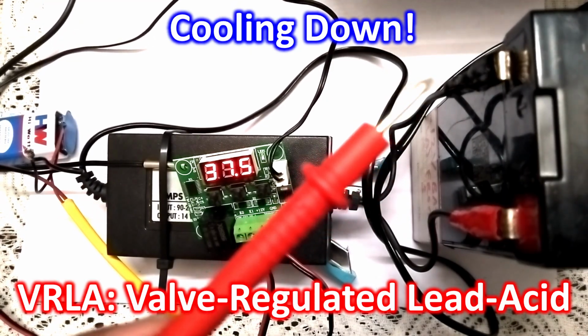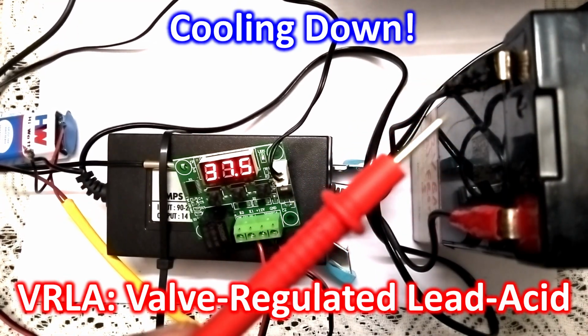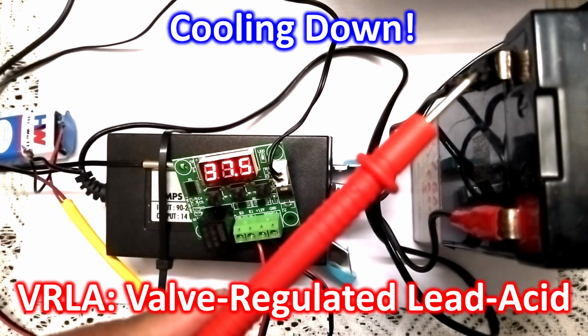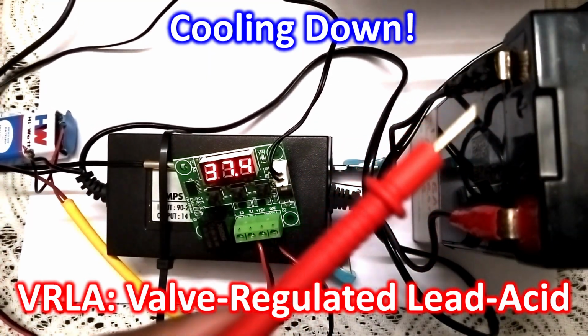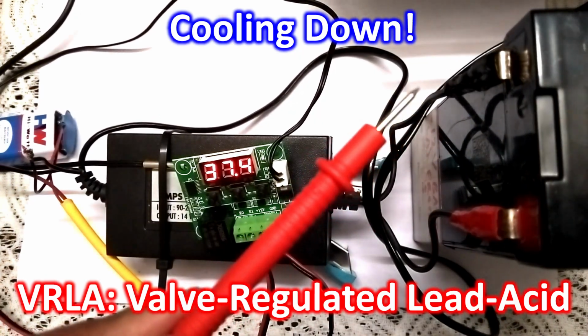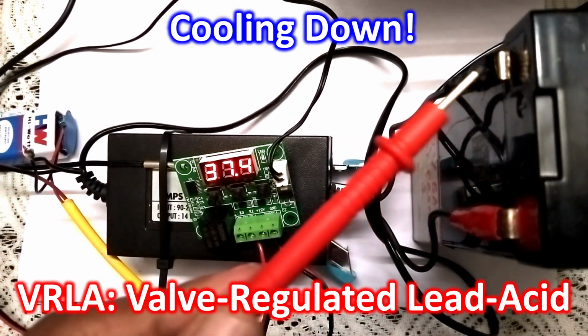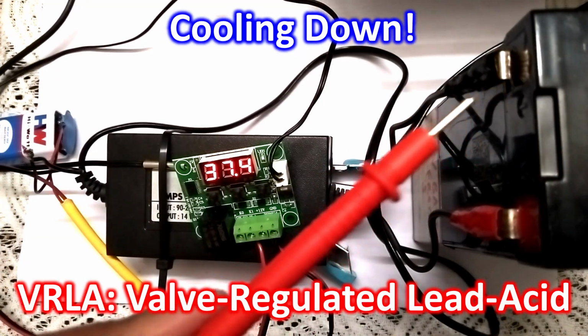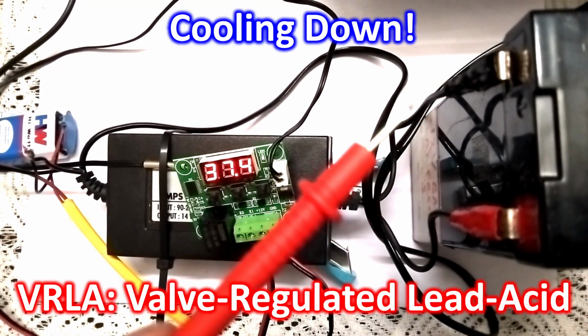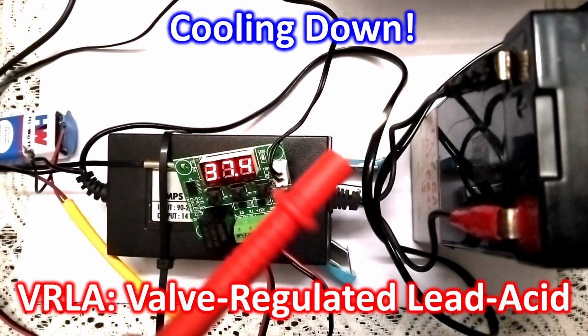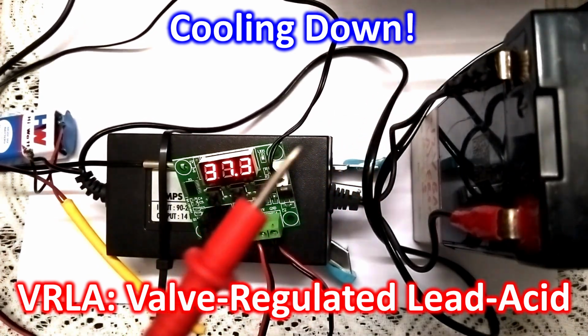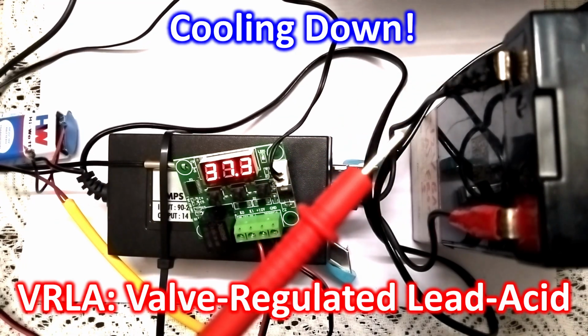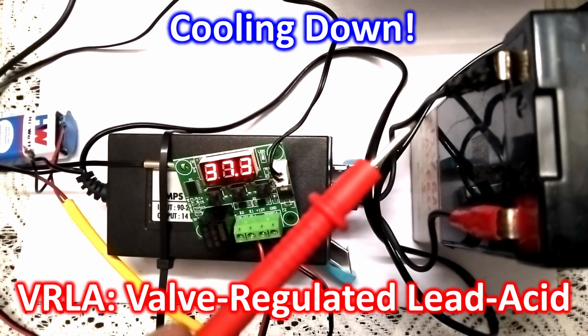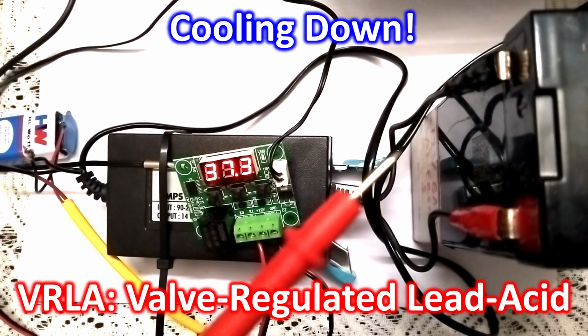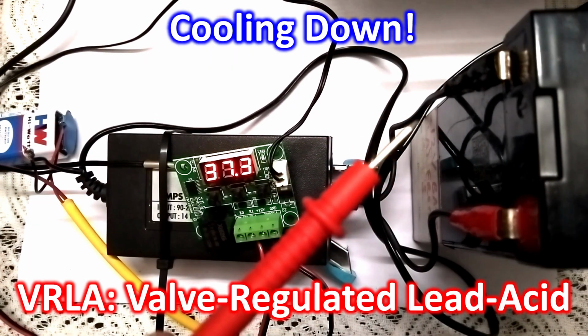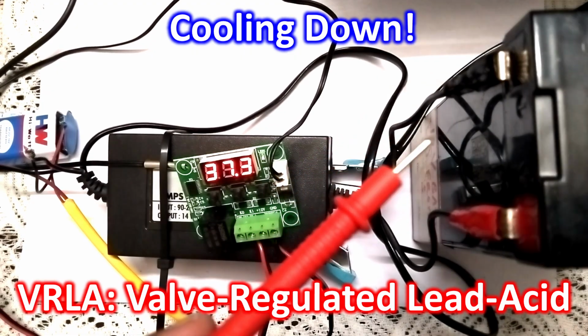Even otherwise, when the usual flooded lead acid battery with a vent is being charged, the room will get acid fumes. This also has a vent, that's why it is also called VRLA, valve regulated battery. But that's only for higher pressure inside, and only a small amount will come out, unlike the usual flooded lead acid battery which will have plenty of acid fumes, especially when kept in a closed room, like most people have the inverter batteries below the staircase in a small room or enclosure. Can't say it as a room.